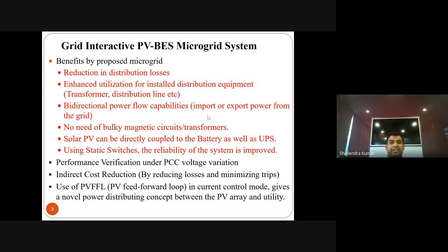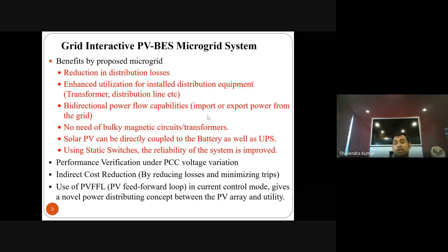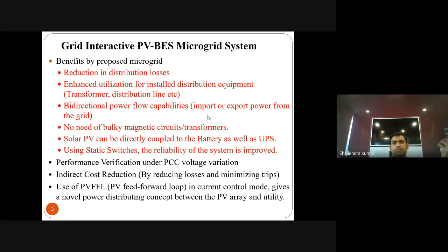On the utility side, for synchronization and desynchronization — addressing grid outage and recovery — we have the point of common coupling where the voltage source converter, non-linear loads, and grid are connected. Between the PCC and utility grid, we use power electronics switches rather than relays or circuit breakers, because relays and circuit breakers have their own delay. Using power electronic switches controlled through a mode transition controller, we can connect and disconnect the utility much faster — in around one to two cycles — which improves system reliability.